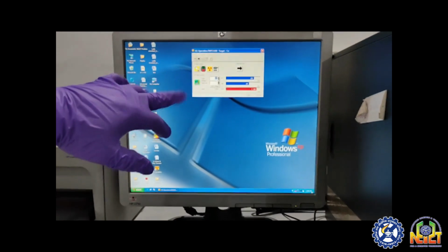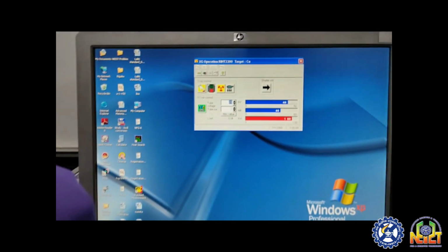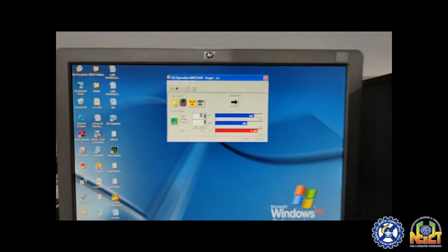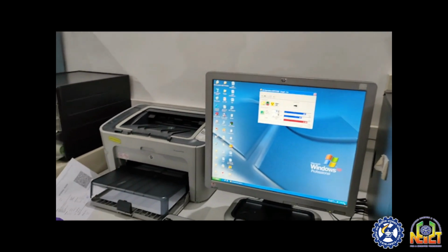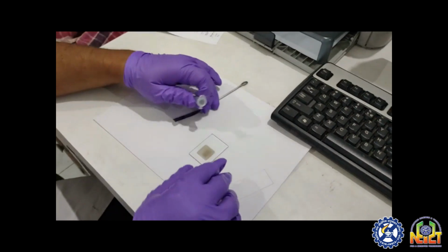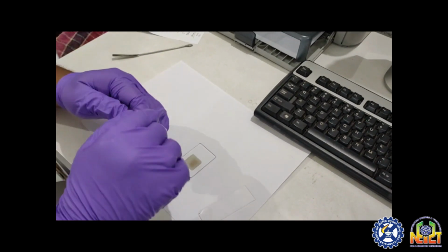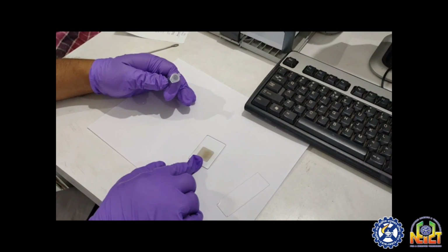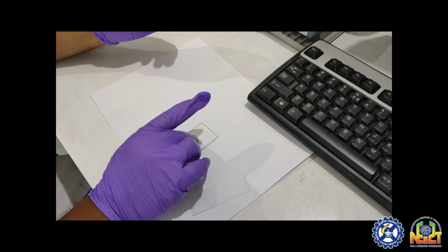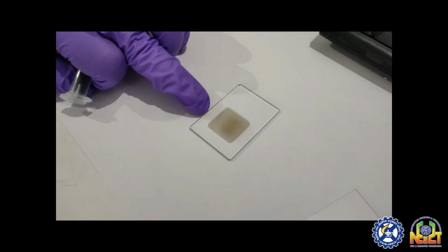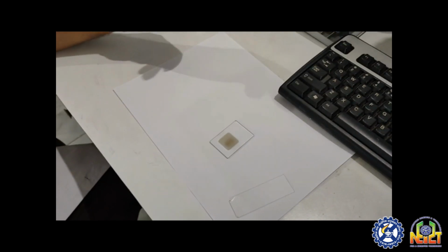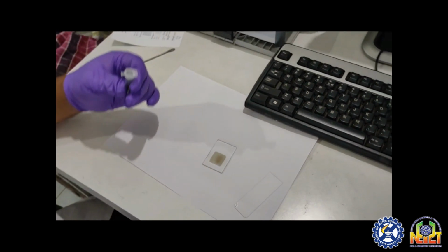Now aging is completed. The voltage and current have reached the requisite level. Therefore, we can proceed towards sample preparation and sample analysis. So now I am going to show how sample preparation is done. This is the sample plate, and we have to keep the sample in this curved part of the sample plate. The required amount of sample is 1/10 of a gram.